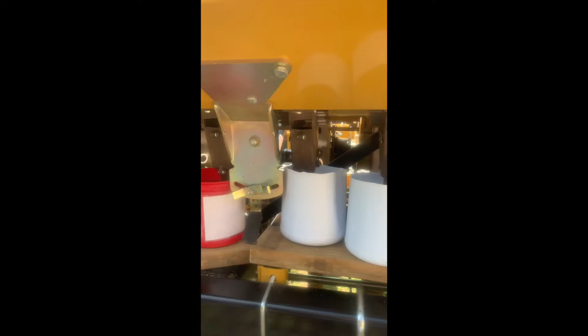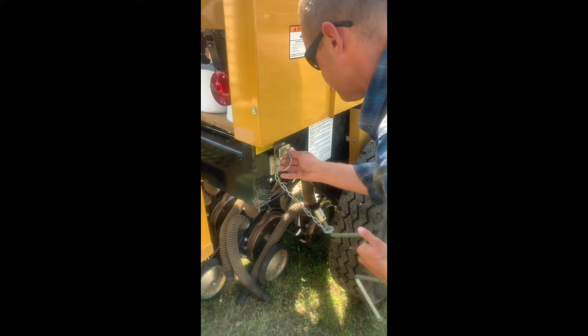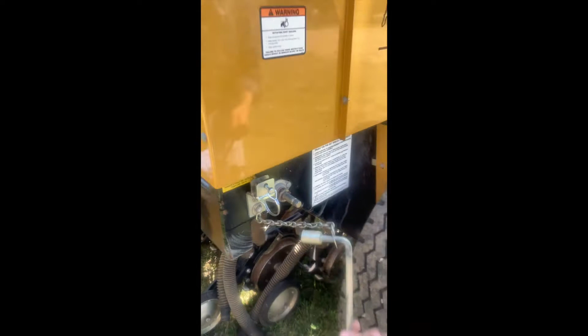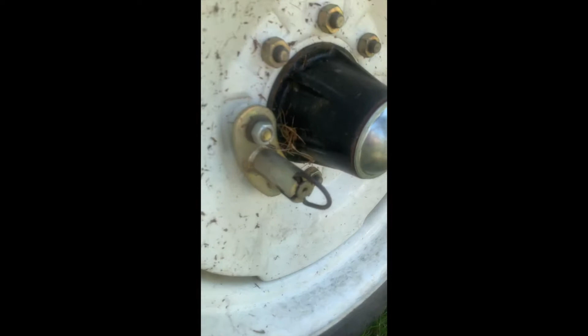Next, I'll move over to the calibration lever located on the side of the machine. You want to remove the clip that holds it, pull the wrench out, and this is the calibration nut located on the side of the machine. You can attach the lever to that. Make sure to rotate it until you capture the pin inside the machine, and make sure the wheel is disengaged so the ground drive is disengaged for the duration of calibration.